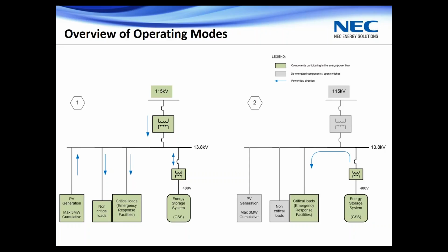working together. And if we were to lose the 115 kV connection and the substation goes down for an emergency event, we would end up switching over to the microgrid resiliency mode of operation, which is shown on the right of the page here. In which case, we would disconnect all of the non-critical loads, and we'd disconnect the PV generation, and we'd start the system back up under the islanded mode. And in that mode, the GSS battery would essentially act as a grid reference.